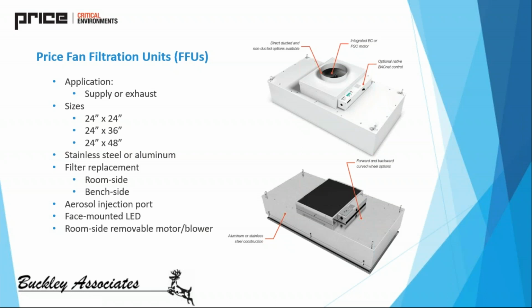In general, a fan filter unit, you've probably seen these before, is just a powered filtration box. It's primarily used in the healthcare industry. Due to typical healthcare applications where we're going to be using these, they almost always come with some sort of HEPA filtration. They have the ability to come with some other filters, but right now I'm going to focus specifically on HEPA filtration. These can be configured in both supply or exhaust applications. They come in standard sizes of 24 by 24, 24 by 36, or 24 by 48, and they're designed in those sizes so they get dropped right into a drop ceiling application. However, these can be utilized in many other configurations, as we're going to see on the following slides.